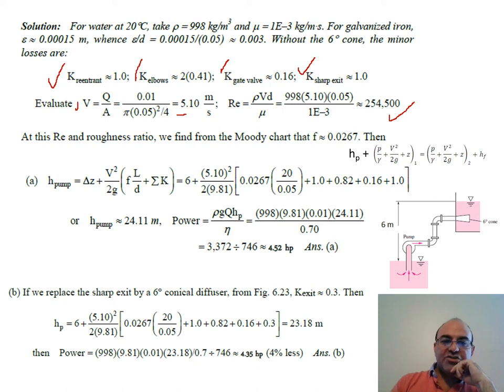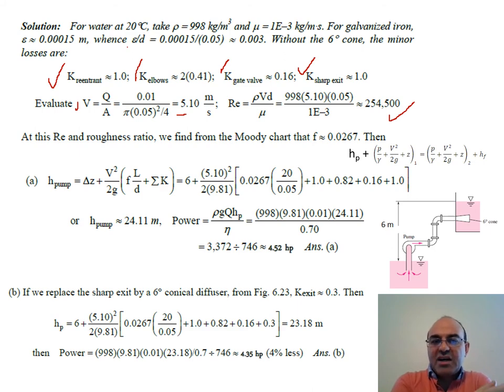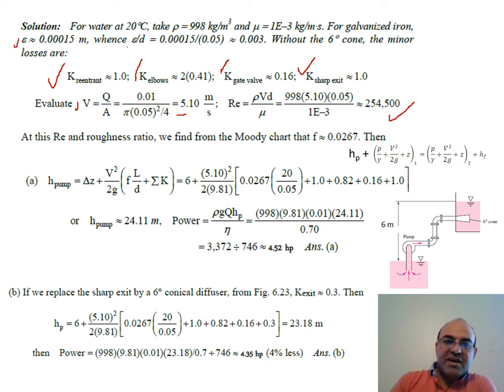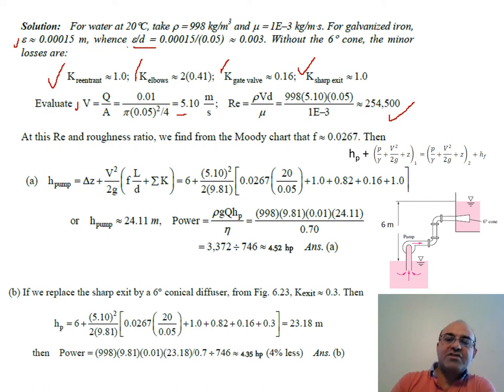For roughness, galvanized iron has epsilon given in the roughness table. We find epsilon/D = 0.003, and with Reynolds number and epsilon/D, we use the Moody chart or Colebrook or Haaland equation to find friction factor f.